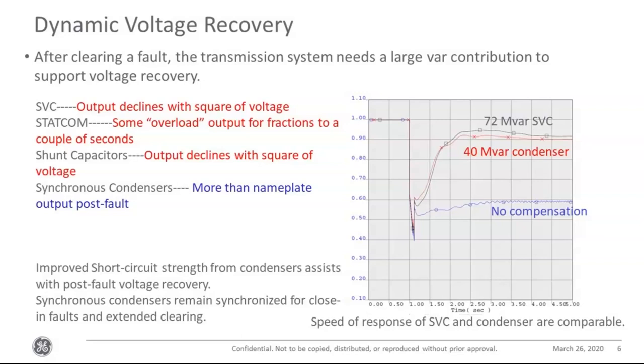STATCOM has some overload capacity where it can provide an overload output for fractions of seconds to a couple of seconds, but even STATCOMs, if you have more severe faults or faults that are for extended duration, might also not give you as good a dynamic voltage recovery response as synchronous condensers. Synchronous condensers can take up to 1.5 to even 3 times the nameplate rating for fractions of seconds to a few seconds, and the higher overload capability is more with static excitation rather than brushless.